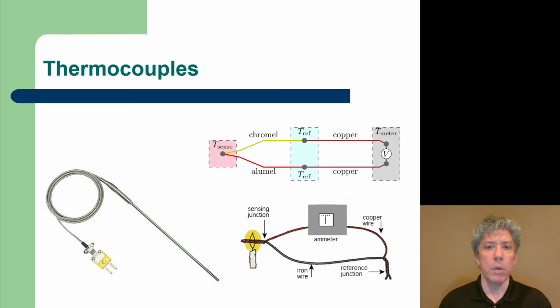So in order to cancel the effect of those junctions, what you have to do is know the temperature at those junctions, and then if you know what types of materials are there, and you know the nature of those, which has already been measured for you, then you can cancel out the effect of the reference temperature and back calculate the sense temperature. Now, the expensive part of a thermocouple is not the wire itself. The wire is relatively cheap, from pennies to at most dollars or so per foot. The expensive part is everything from the reference junction back, because you have to have some other method for measuring the temperature at the reference junction, and of course you have to have the associated electronics in the meter in order to calculate the sensed temperature.